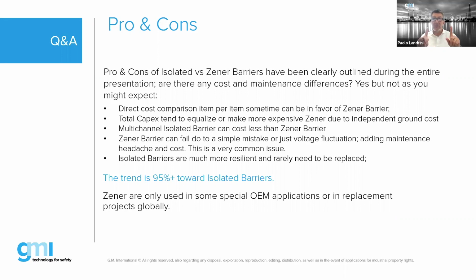But when you take into account, as Andrea explained earlier, the overall CapEx cost—the grounding you have to create for it, and the maintenance of that grounding, because by standard it must be inspected and verified. To do so you need a redundant ground connection, because if you disconnect ground, you're no longer safe. So how can you check the ground without disconnecting it? Well, you either shut down or you have to have a redundant ground. So these wiring and grounding costs go beyond the cost of the item, and must be taken into consideration.